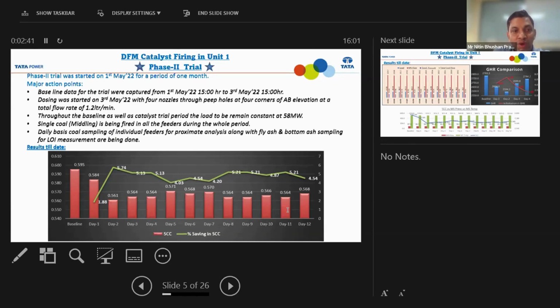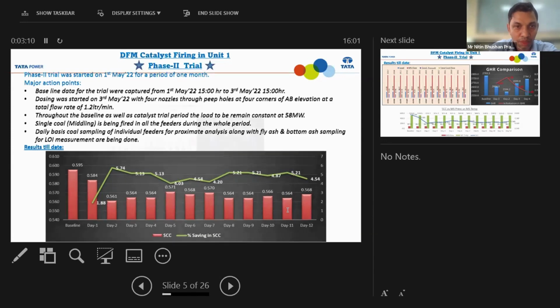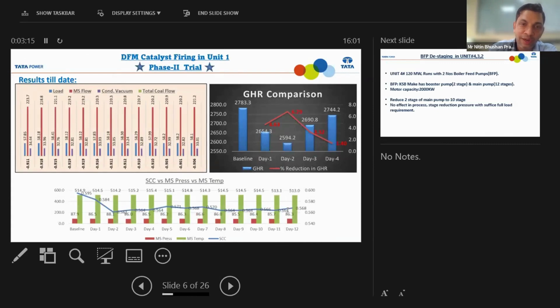The final impact of the system was a decrease in specific fuel, in the order of around, as you can see in the graph, 5. We started with day 1. On day 2, we decreased the specific fuel to 5.74, then 5.3, and you can see that on average 5.2 specific coal was decreased. In terms of heat rate, our baseline is about 2783, and day to day heat rate we calculated with the reduction of coal. Day 1 we achieved 2654 heat rate, and consequently there was a decrease in the heat rate of around 4 to 5 kcal.